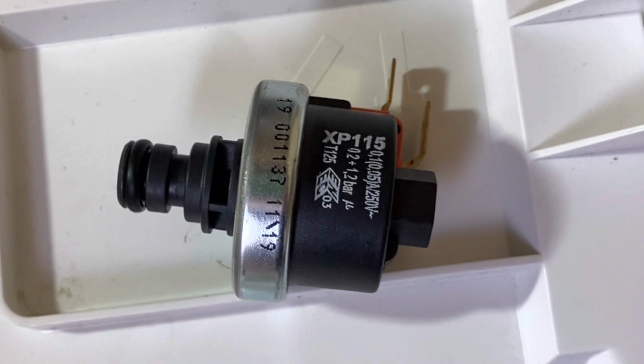Inside, it's just a little diaphragm and a spring mechanism, which when the pressure increases, forces the piston onto the micro switch, so the contacts change as pressure increases and decreases. So it opens and closes with pressure. Some older boilers, again, used 3 contacts, and they had common, normally closed and normally open. I think depending on the way that the pressure was read, again, they could work in reverse. So I'd check with the manufacturers, if you're on an older type boiler with 3 contacts, give the manufacturers a ring and just check which way around it works.